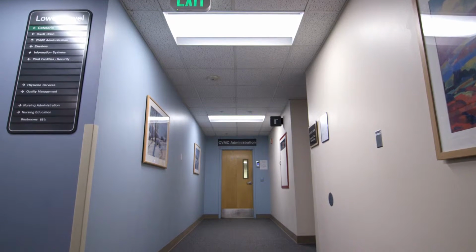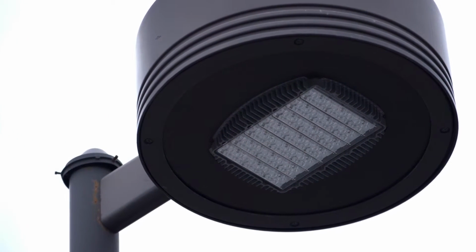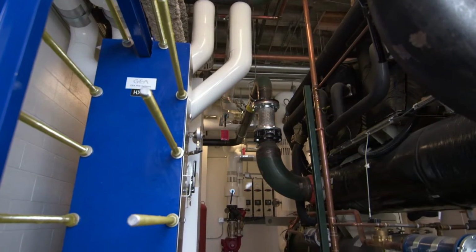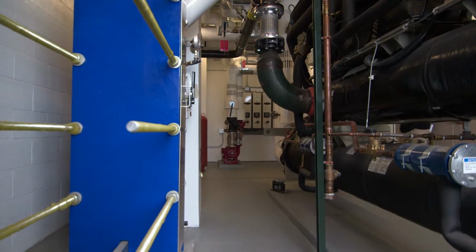and for our employees. By having this mindful, thoughtful approach to energy efficiency and focusing on the root cause, we've actually been able to take a more preventative and proactive maintenance approach to all of the infrastructure here. We've been able to reduce the electricity consumption here by 19% and fuel oil bills by 29%. So across the board, a BTU input reduction of 26% since when we started back in July of 2010.